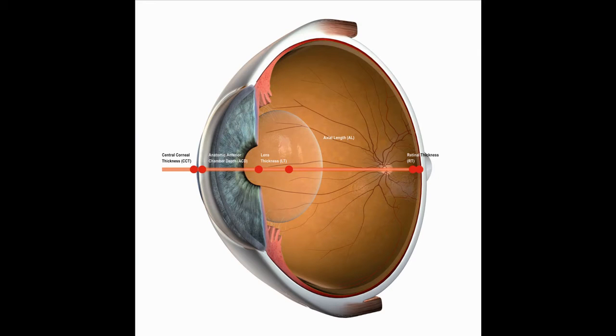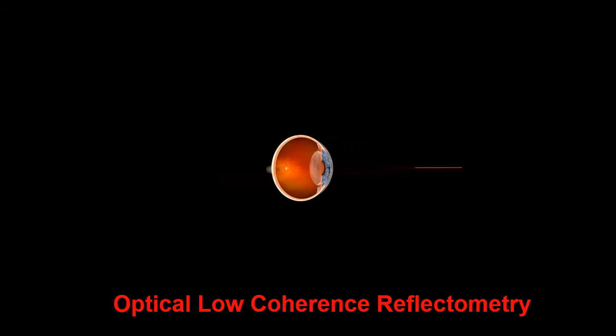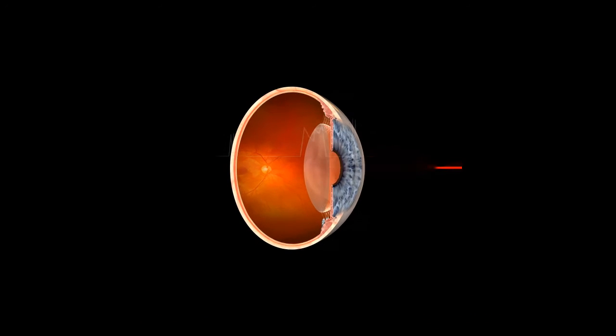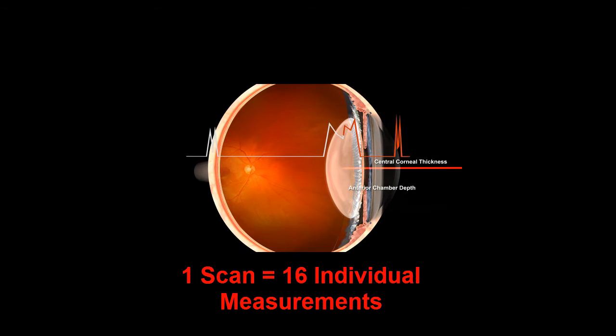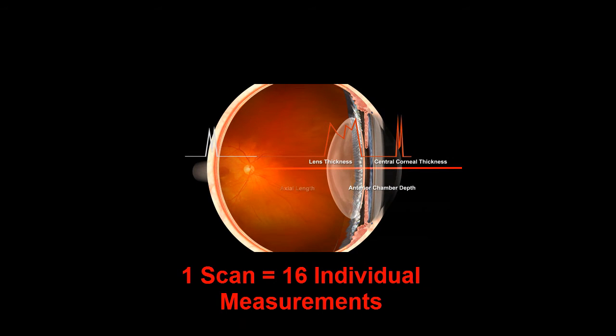Lens thickness measurements are captured along the patient's visual axis, producing highly accurate and reproducible measurements. LensStar utilizes optical low-coherence reflectometry to measure lens thickness, a technology similar to time domain OCT. Each scan is composed of 16 individual measurements.